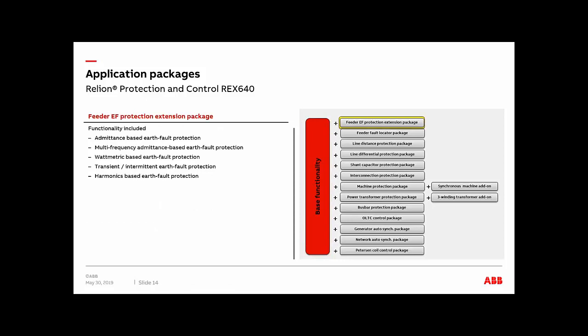Now moving on to the first package, which is the feeder protection, with extension package for ground faults. So mainly on this package, you're going to get everything that we saw on the base, plus admittance-based earth fault protection, multi-frequency admittance-based earth fault protection, wattmetric-based earth fault protection, transient and intermittent, and harmonic-based.